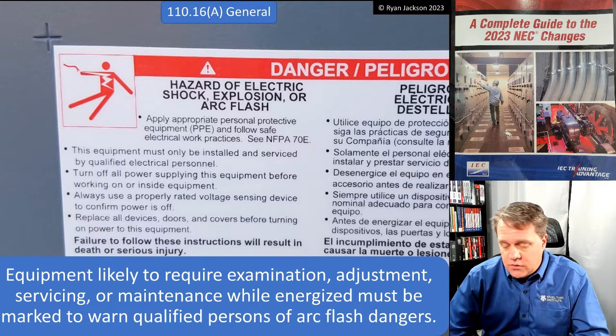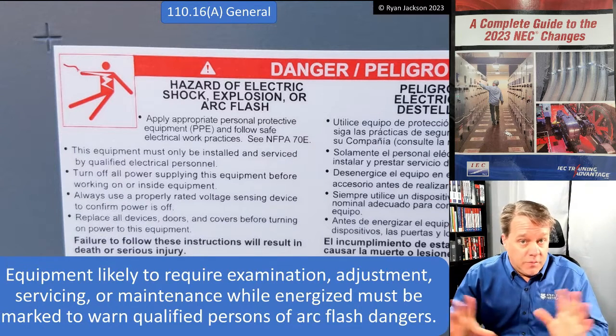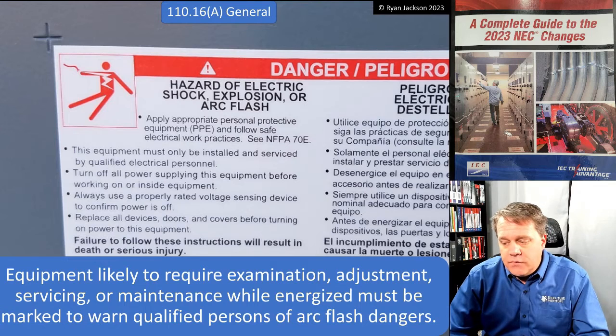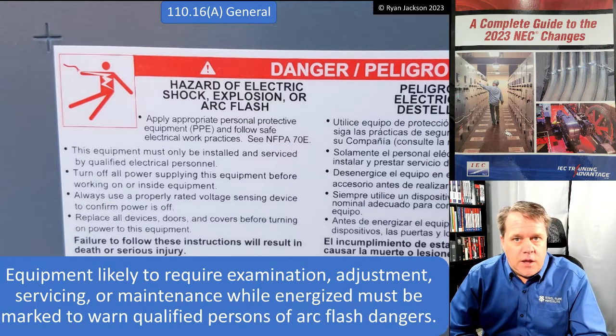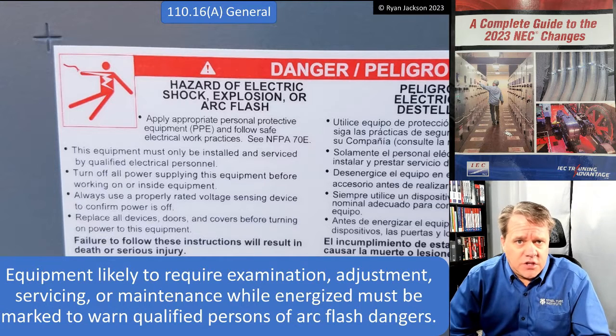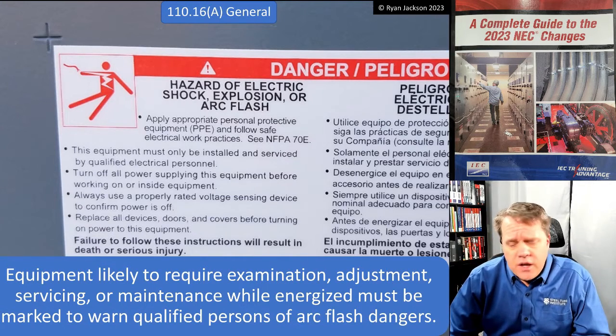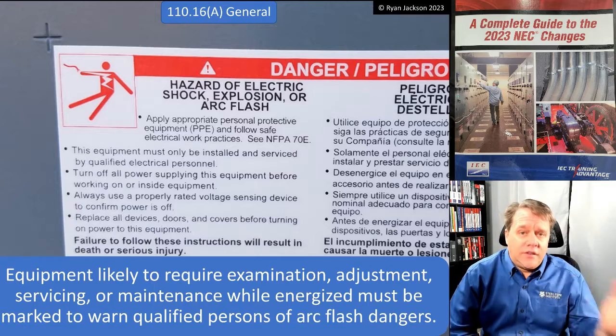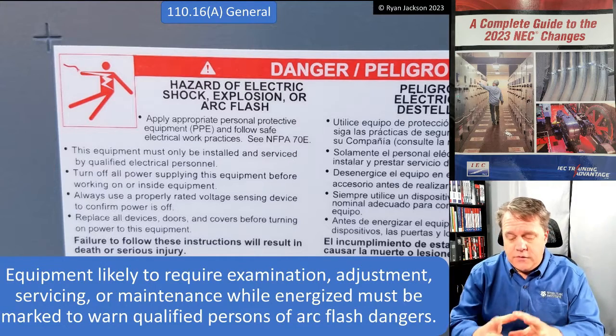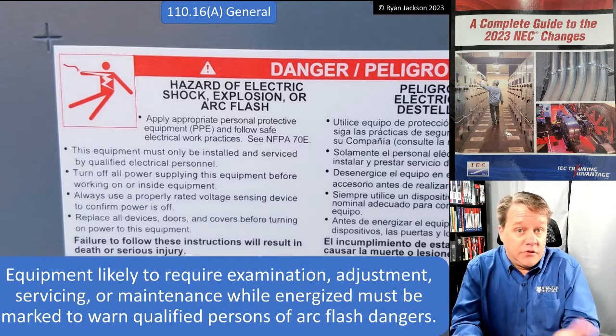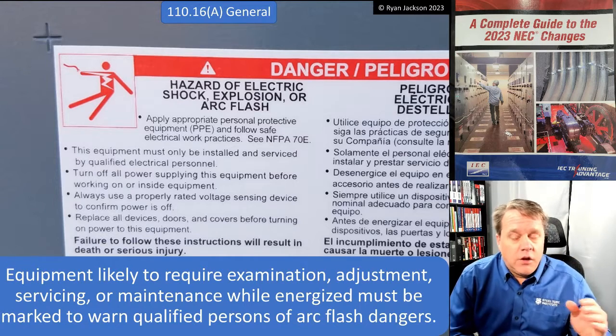themselves hurt. So look, I'm not going to turn this into a whole big safety rant, but OSHA and 70E both say that you need to be working in de-energized conditions, all right, an electrically safe work condition. And that means it's shut off, it's tagged out, it's verified the absence of voltage and some other steps as well.